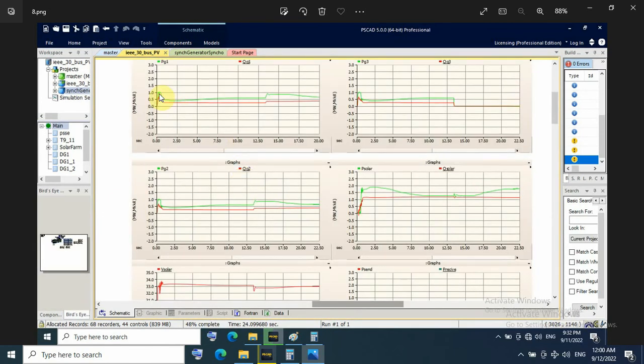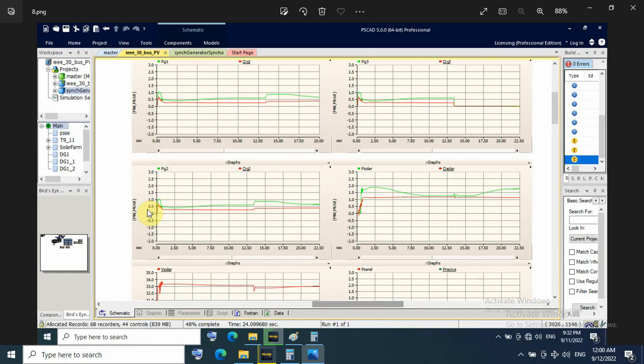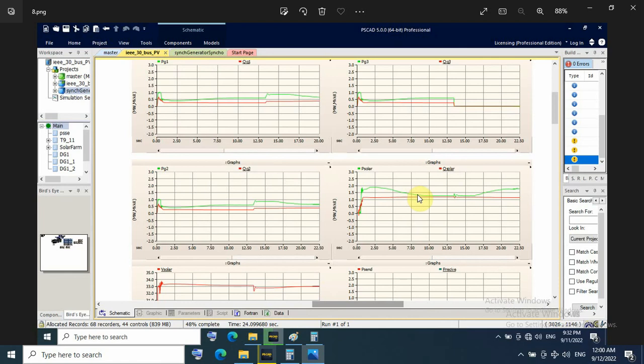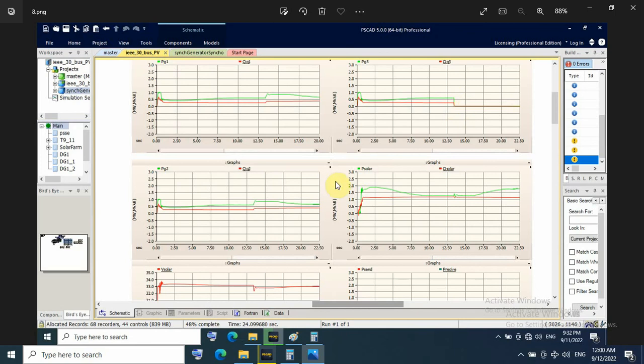Here the measurement on graphs. Before PV starts to generate, each genset takes about 1 megawatt for load of 3 megawatt. After that the PV starts to generate power. So the load on genset decreased to 0.5 megawatt, from 1 megawatt to 0.5 megawatt on each genset. Then here PV starts to decrease. At the same time load increase on DG. So the load increase on DG to 0.8 megawatt.